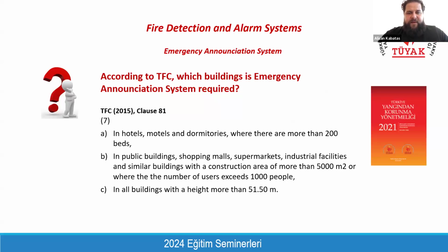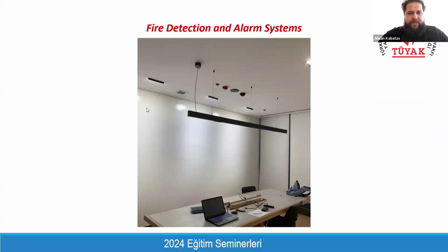And in hotels and dormitories having an occupant load more than 200 beds, or public buildings having an occupant load more than 1,000 people, or in high-rise building having a construction height more than 51.5 meters, we need to provide this emergency public announcement voice alarm system.